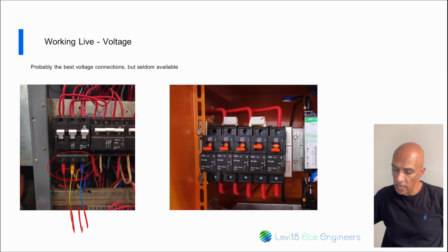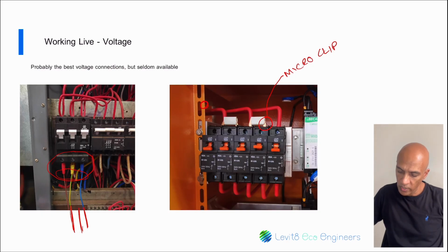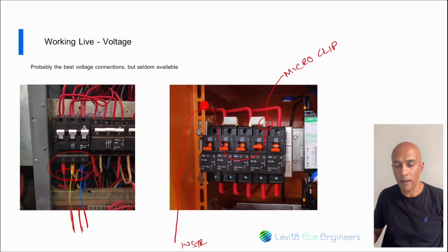Now when we're looking at this connection here and using the micro clip, you're going to have the weight of the cable pulling that micro clip down. So in this case, a good spot to actually cable tie your lead would be up here. Your lead would be coming down from the instrument, hanging down here, and then you'd have your micro clip going onto there. So this is always essential to do it this way.